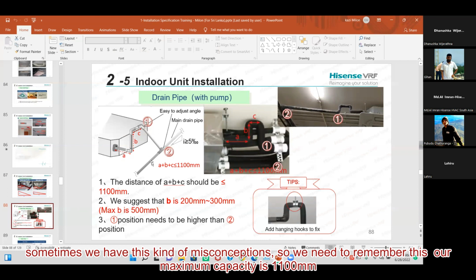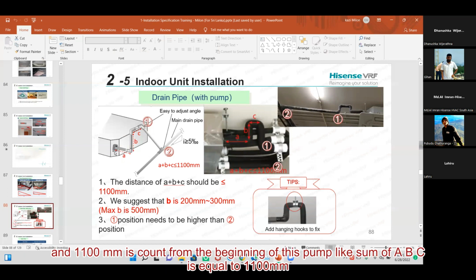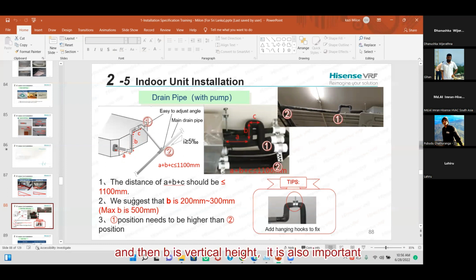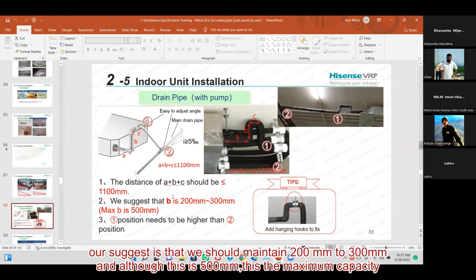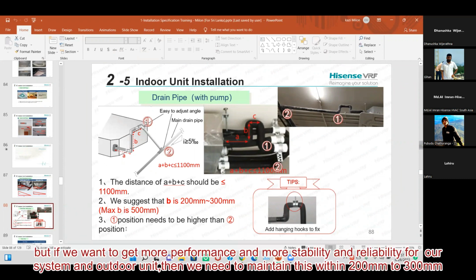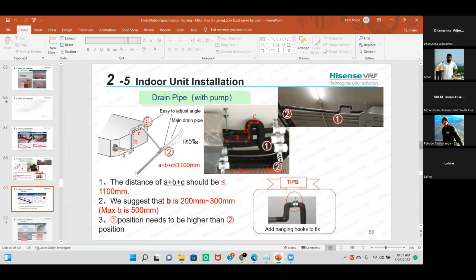Our maximum capacity is 1100 millimeters, counted from the beginning of the pump, so the summation of A, B, C is equal to 1100 millimeters. B is our vertical height, and it is also important. We suggest that B should be maintained at 200 to 300 mm. Although the maximum capacity is 500 millimeters, if we want more performance, stability and reliability for our indoor unit, we need to maintain it within 200 to 300 mm.